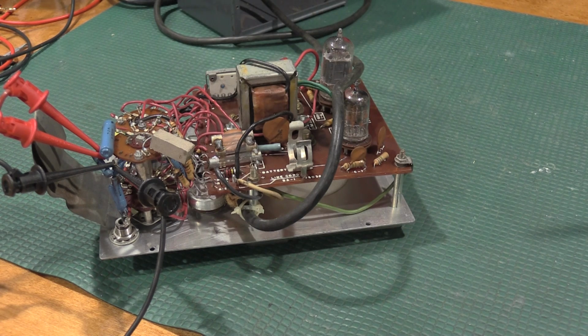This means I won't be able to calibrate the ohms range, which is totally fine. Everything else in the meter will work, and it won't be affected. Also, some of the other equipment that I'm giving them, they'll have ohms measurement capabilities with other meters. So not having the battery in here is going to be a better solution than having the battery in here and having it blow up again. Where we're at now is I have to warm up the calibration gear and see if we can calibrate this meter.